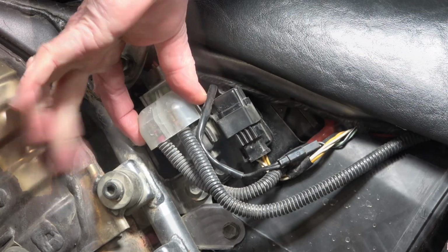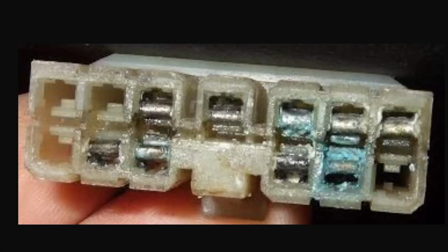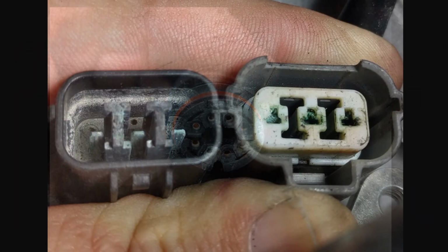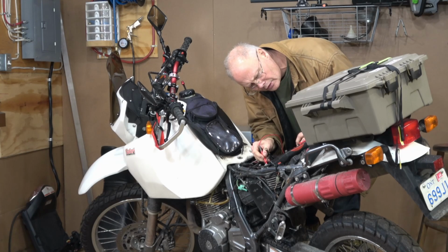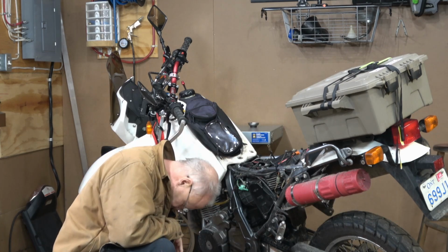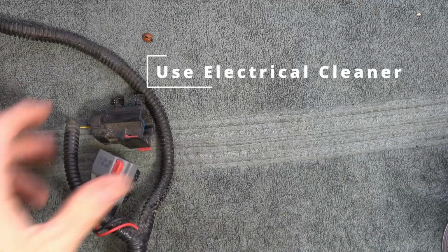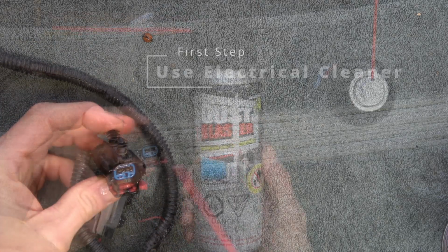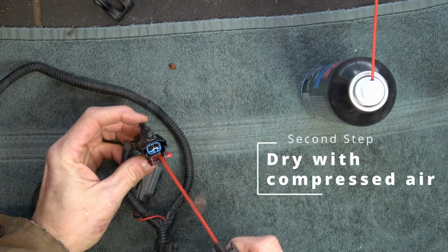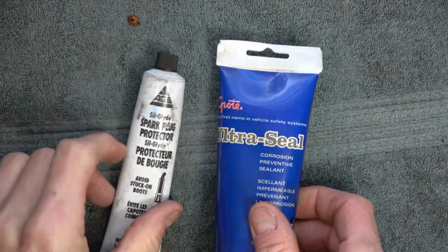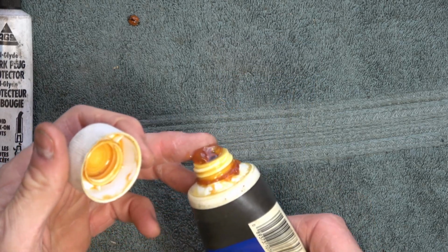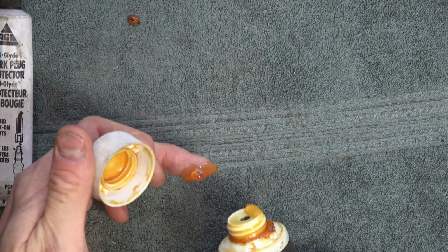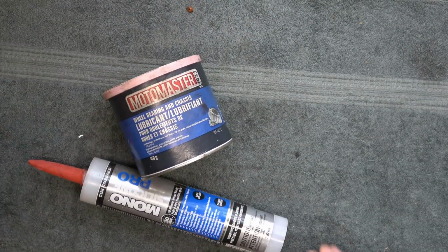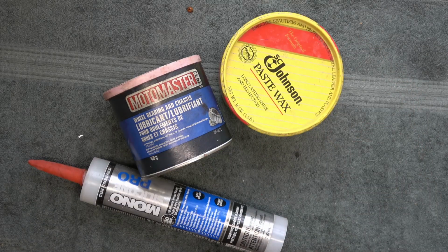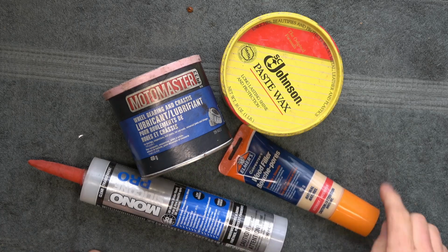Corrosion-causing moisture can enter these electrical connectors and cause poor electrical connections, leading to component failure. Troubleshooting an electrical circuit with one or more corroded electrical connectors can be both time-consuming and frustrating. When reconnecting electrical components, pack them in a dielectric grease compound. Dielectric grease is specifically formulated for sealing and waterproofing electrical connections without interfering with current flow. Use only dielectric grease compound or an equivalent for this specific purpose. Do not use a substitute that may interfere with current flow, such as just regular grease or silicone sealant. These really aren't the right product to use.